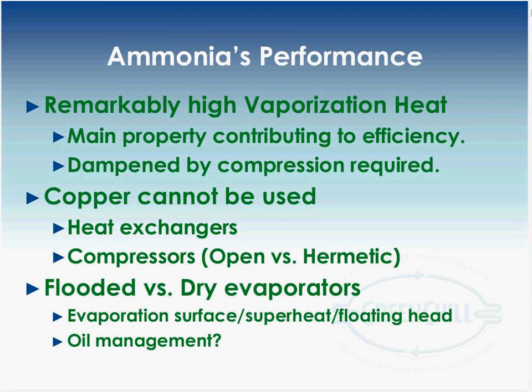In the end, I know it's kind of vague to say this, but ammonia does prove to be a superior refrigerant efficiency-wise, and that's not typically debated. One of the factors that plays into it is copper. Ammonia, when it comes in contact with copper, forms a precipitate inside the system, which is not a good thing, and that affects your heat exchangers and your compressors. Obviously, you have to use a steel heat exchanger. The most common is a stainless steel heat exchanger. They do make copper heat exchangers with a coating to protect them from the ammonia, and you can get more efficiency out of those.